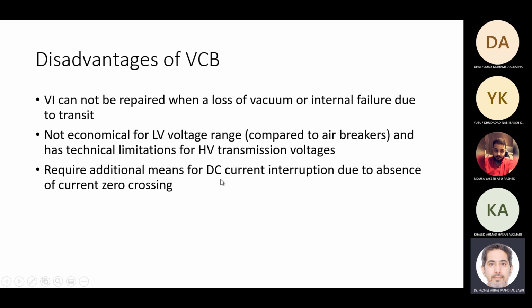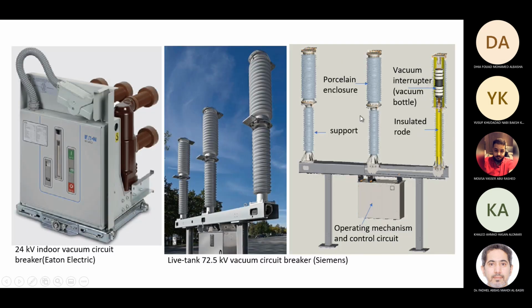The problem with vacuum is that when you deal with decaying DC, it requires the current to pass through zero. So with generator breakers, where the current does not cross zero initially, this will create a delay in opening the breaker, because you don't have a zero crossing, as I will show you, inshallah, on different slides. So it could be a medium voltage breaker with the vacuum tubes here, or a high voltage breaker with the vacuum tube somewhere here, like in this one.